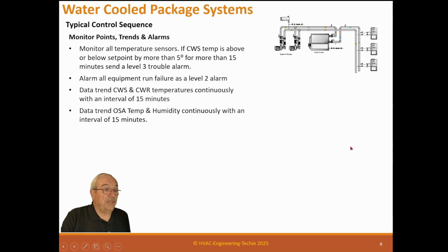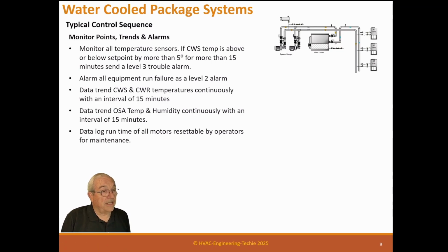So it doesn't take a lot of data, but it does show you what's been going on. Now, if you need real close diagnostics, you need to set up a trend a lot closer in time than 15 minutes. But for an operator continuous trend, 15 minutes is fine. Data trend outside air temperature and humidity, the same, every 15 minutes. Data log runtime of all motors. So we're going to just keep track of the runtime of motors so the operator can see that, and it's resettable by the operator in case he has to change a motor. So if he changes a motor, he needs to reset the time back to 0 hours.